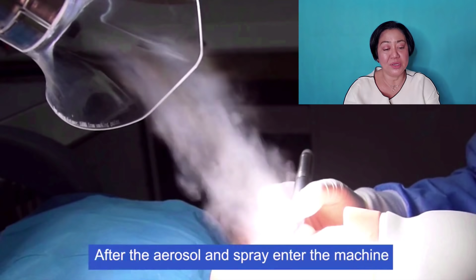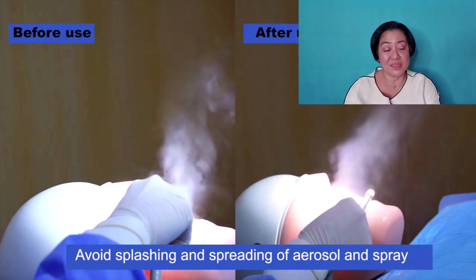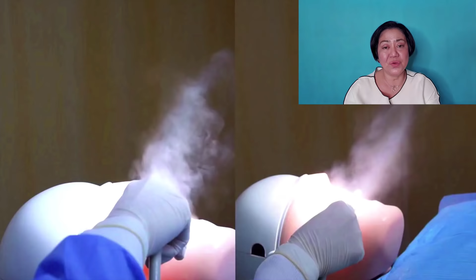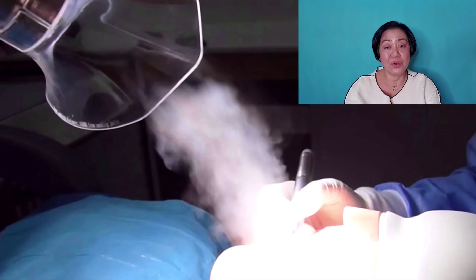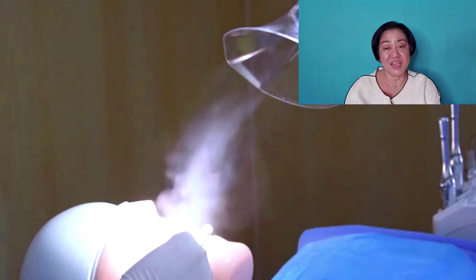My opinion is that once all the aerosol it sucks goes through this area, you again need to maintain it. You need to clean this, because this area where the aerosol passes through is contaminated. So that is extra work for you. Plus, there are also consumables, which are filters. You cannot allow the filter not to properly work, otherwise you wasted money investing in such equipment. So for me, if you cannot maintain it and you don't have extra money, this is something I will not say you should buy.